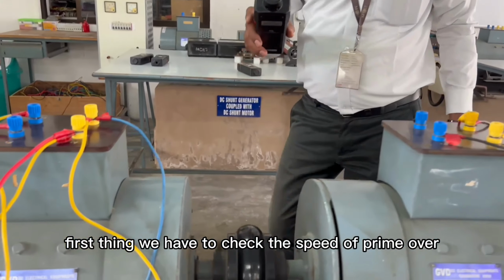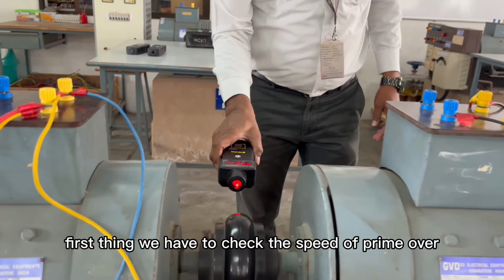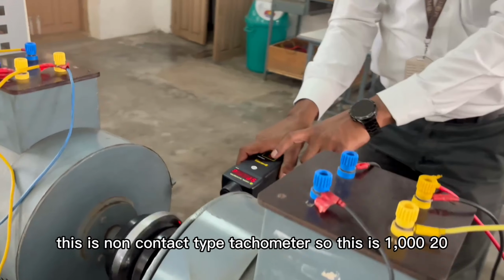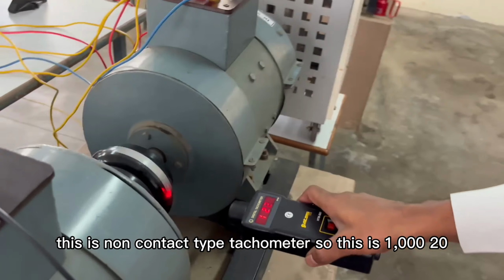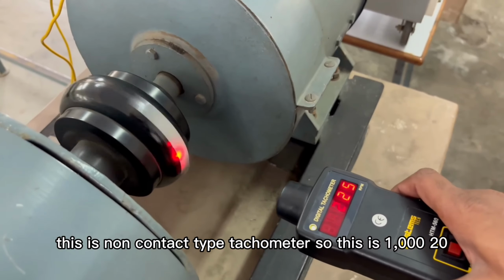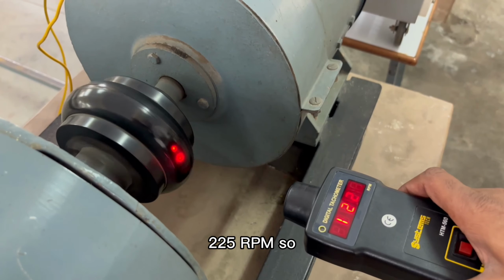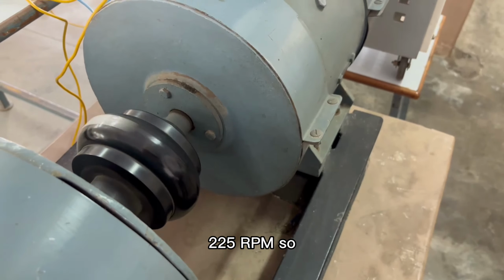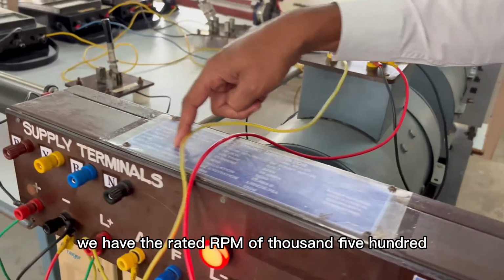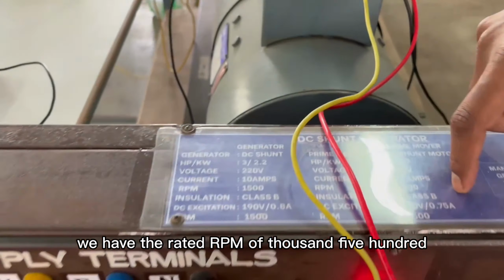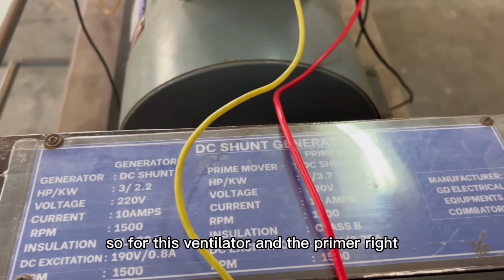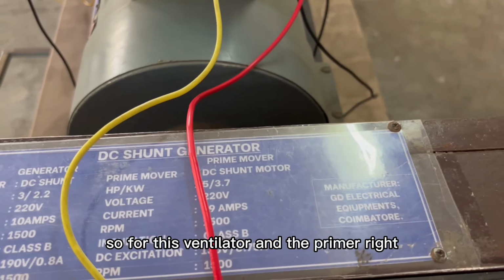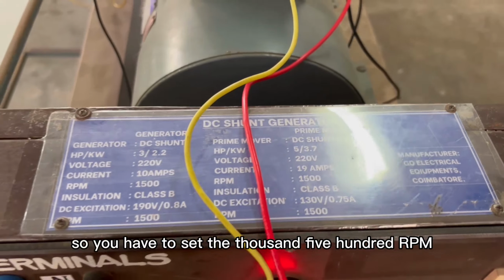First thing, you have to check the speed of the prime mover using the tachometer. This is a non-contact type tachometer. It shows 1020 RPM. But actually the rated speed of 1500 RPM is for this generator and the prime mover, right? So you have to set 1500 RPM.